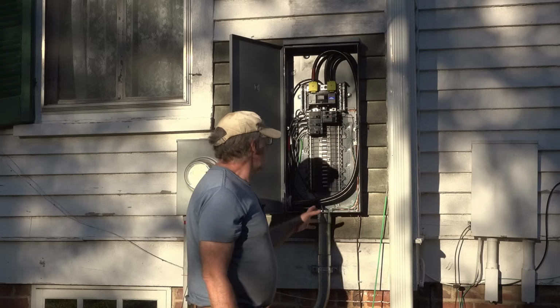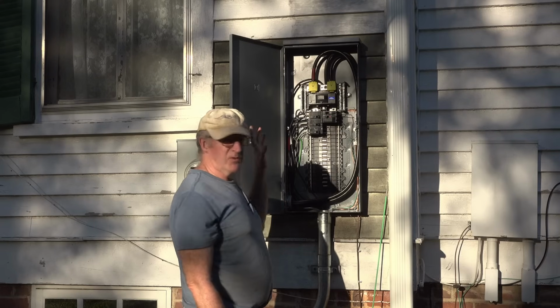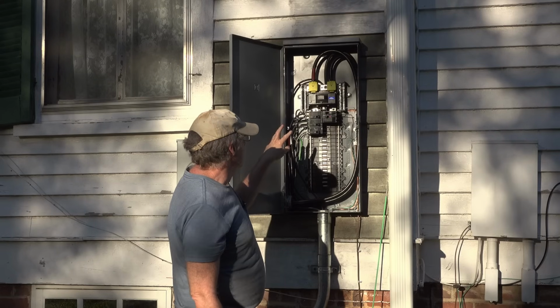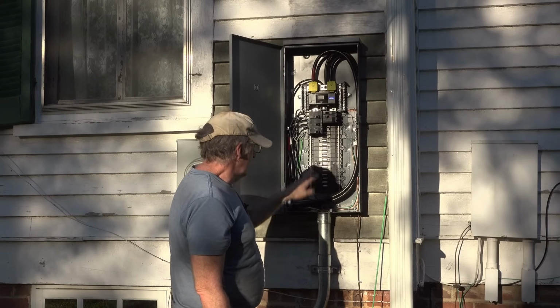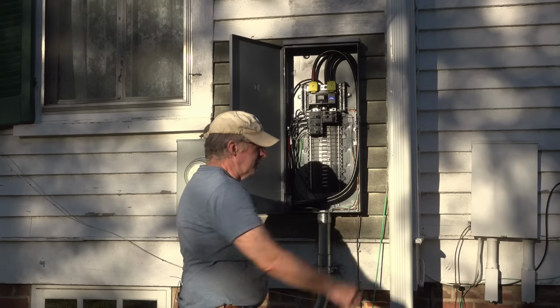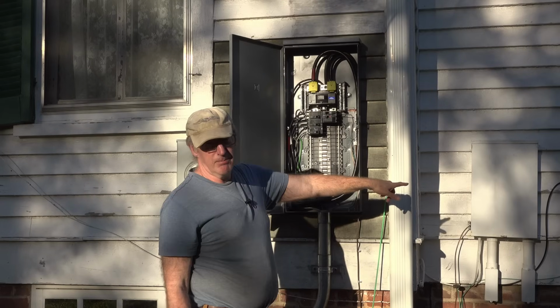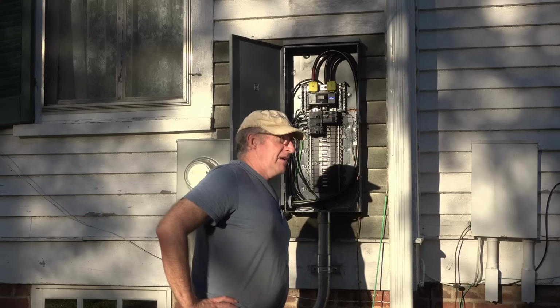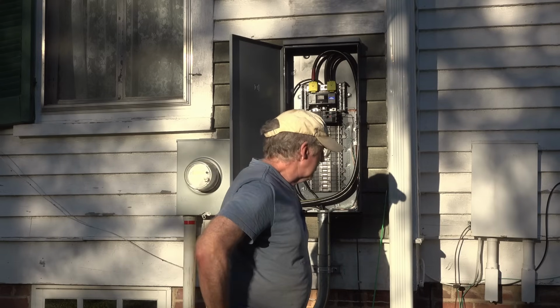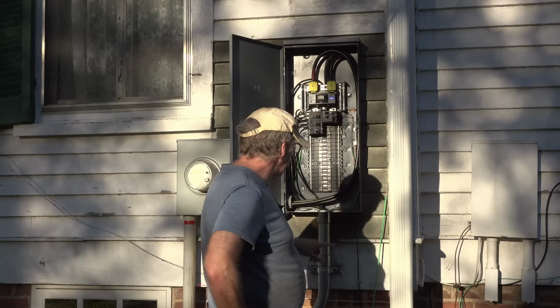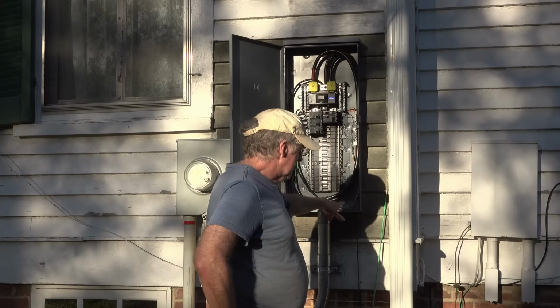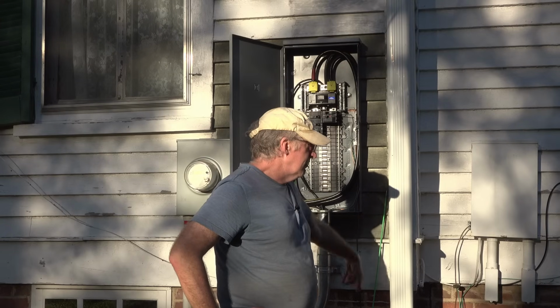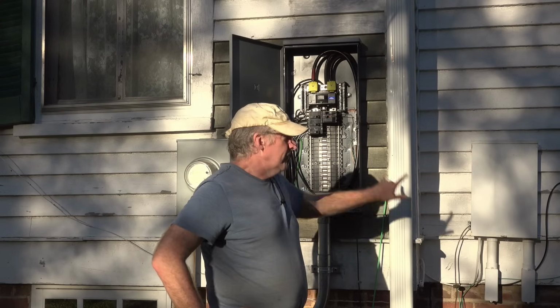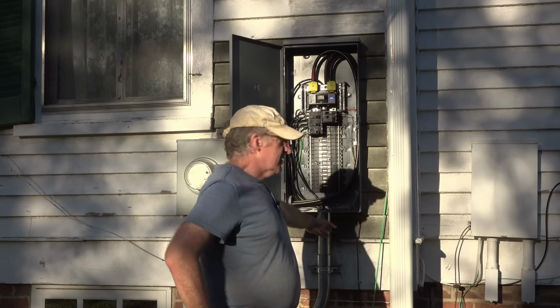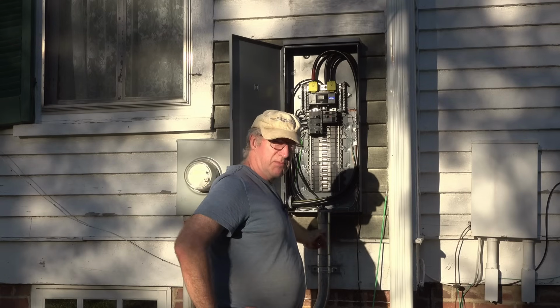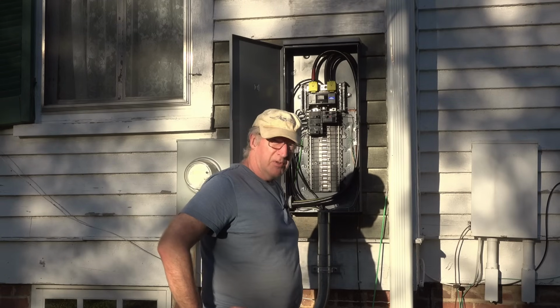One of the problems is that when we first hooked this up, we took 3 very large wires and ran it down through here, behind the brick wall, and came up to power up that box over there. And I'm starting to rethink that philosophy. I think what we should do is put a conduit here outside and run it over to power that box, and get those 3 heavy wires out of this conduit right here, because we really need the space for things that really matter.